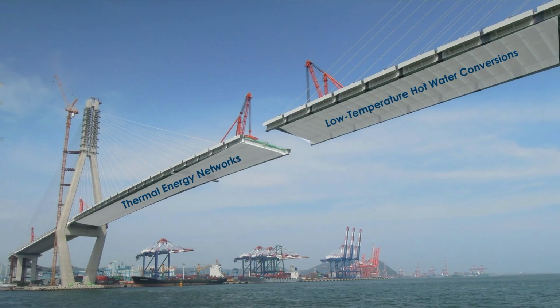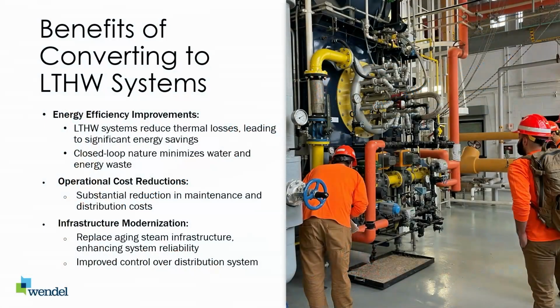Benefits of converting to low temperature hot water: you obviously get energy efficiency improvements. Low temperature means less heat loss for the run of pipe in the building. And in the case of steam, since it's a closed loop system, you're not witnessing energy loss through dumping condensate or having failed traps and venting steam.